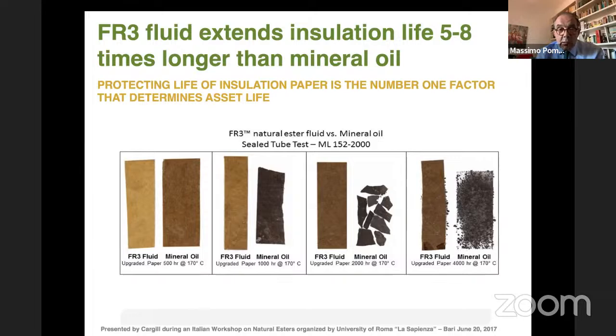The second box is after 1,000 hours, same temperature, and the comparison is again between natural ester liquid and mineral oil. You can see that this paper with mineral oil, left in contact with the mineral oil for more than 40 days, 1,000 hours, became practically black.